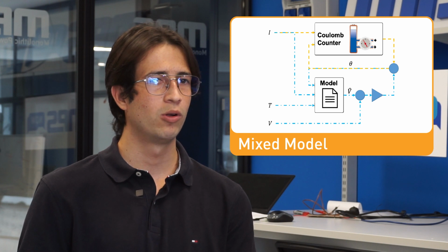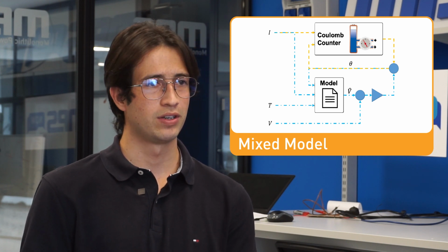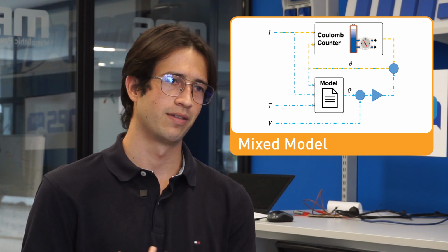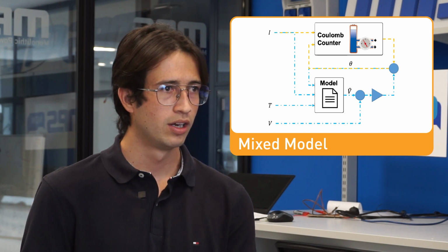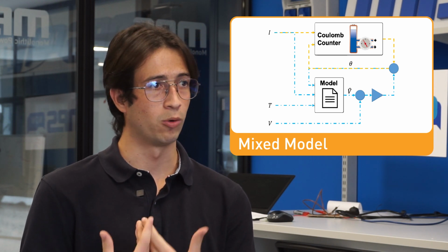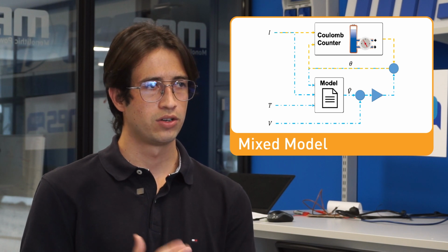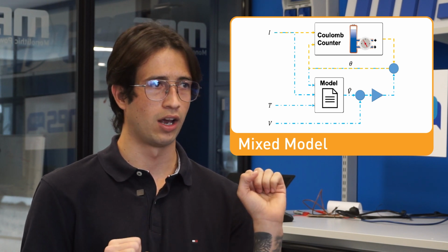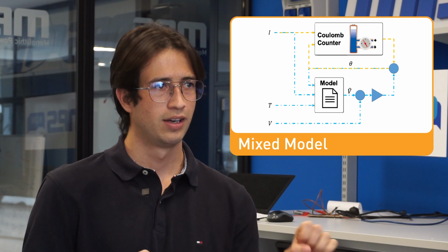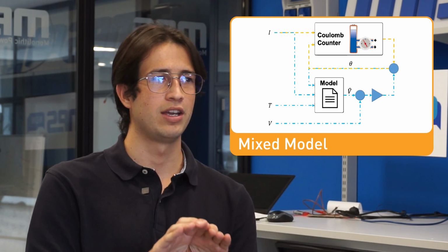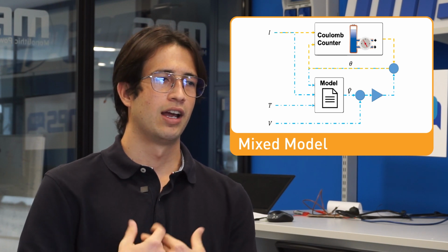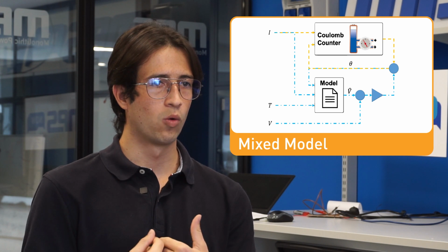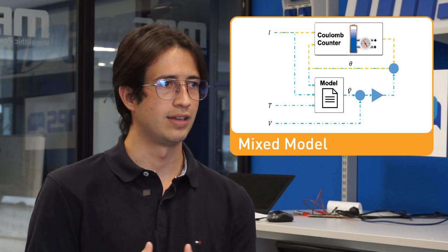This voltage method approach uses a cell model, a very accurate mathematical cell model, in order to estimate the voltage in each iteration. So we basically use the Coulomb Counter measurements and this voltage estimation, we combine each other so we can deliver a really accurate state of charge, because we can correct the state of charge in each iteration, right?